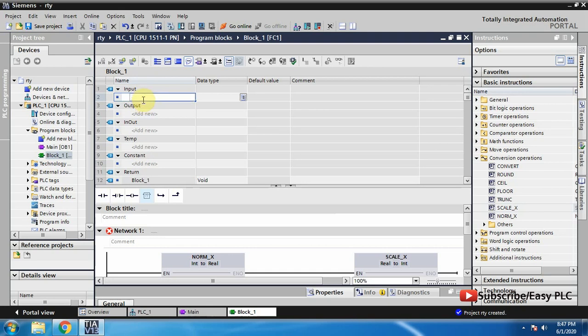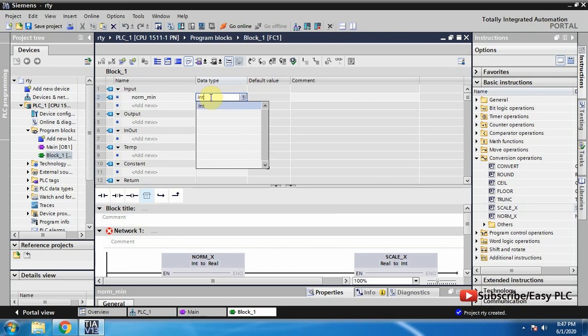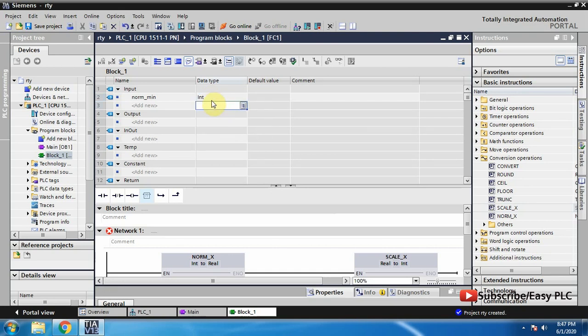As you can see, a function has the option to add input and output tags. Here we can make tags and assign data types for these data tags. We can now make the tags for inputs and outputs required for the NORM and SCALE instructions.